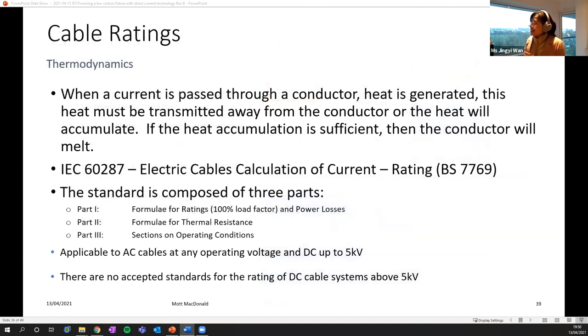Okay, the next topic is about cable ratings. For cable rating, this is all about thermodynamics. It is mainly about how we get the heat away from the conductor while it is operating. So in theory, we can actually use a 1 mm² conductor and have 1,000 amps as long as we can stop the conductor from melting. This is actually related to superconductors, but maybe we can talk a tiny bit more about this later.